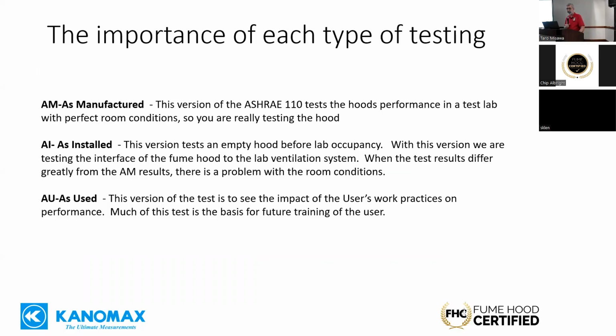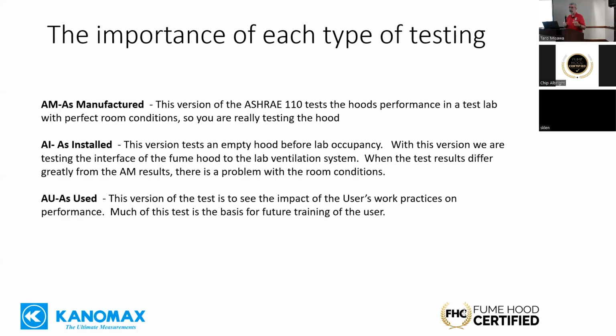Let's look at the types of ASHRAE 110 testing. The first type is as-manufactured. The test protocol is the same for all three, but in an as-manufactured test, you're testing the hood under perfect conditions—an ASHRAE test lab has absolutely perfect room conditions. So what you're really seeing is how well that hood performs.